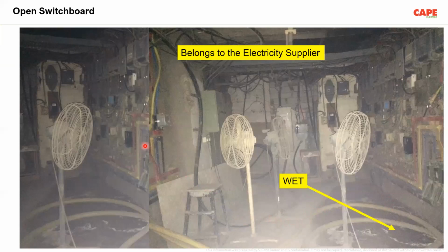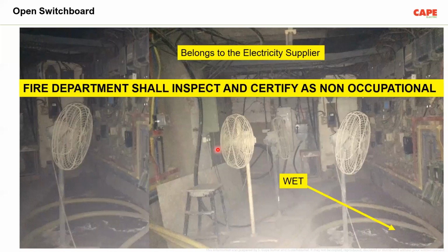If we operate our electrical installation in this fashion, I would say this is one of the worst installations I saw in my life, and this belongs to a utility. And if this kind of installation exists in a city like Bombay, even in 2022, it's not a surprise to say that 80% of fires are from electricity. I would say even 100% of fires are from electricity if we go for these kinds of unsafe installations. It's highly dangerous. The best thing we can do is, I request the fire department, probably in Bombay, please open the meter boards of the multi-story buildings, and if you see these kinds of installations, you can certify that these buildings are not fit for occupation. That is the only way to stop such bad installations.